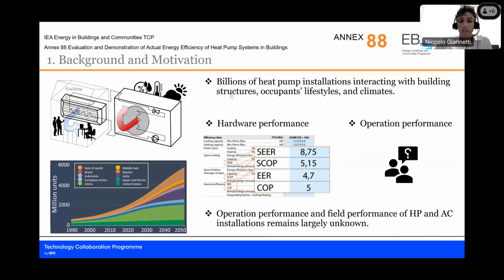We know that the hardware performance of these systems is relatively well represented by current standards. So we have current standards that can give us a clear number about how efficient a heat pump is when tested according to these performance rating standards. But for some reason that we will investigate and describe later, even though we have such an extensive application of this technology, we do not have a clear knowledge about their operational performance. So how these systems actually operate in the field, and how efficiently they operate when interacting with the actual field environment and when operating with their own native control.